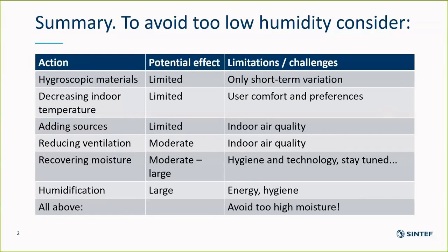To avoid too low humidity we should consider a combination of the following actions: using hygroscopic materials, decreasing indoor temperatures, adding moisture sources, reducing the ventilation rate when appropriate, recovering moisture, and in some situations also consider humidification. For all the above suggested actions it's important that you avoid moisture getting too high. There are some limitations and challenges to all these individual actions, so we're not ready to recommend a very specific package, but these would be the elements.